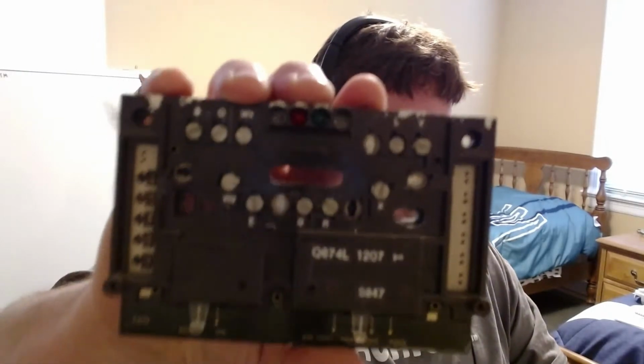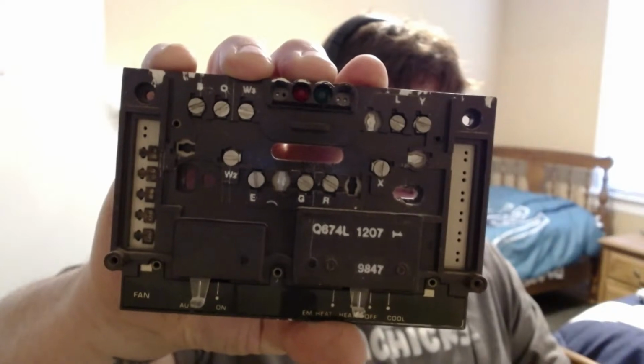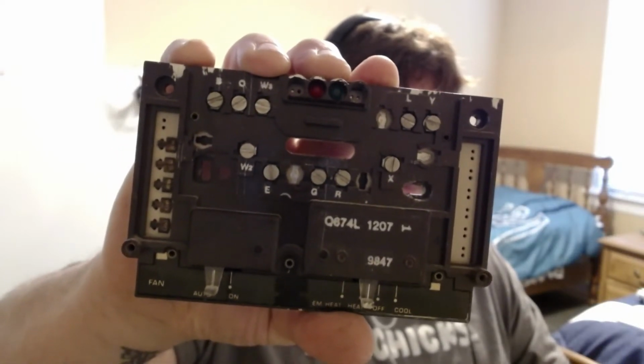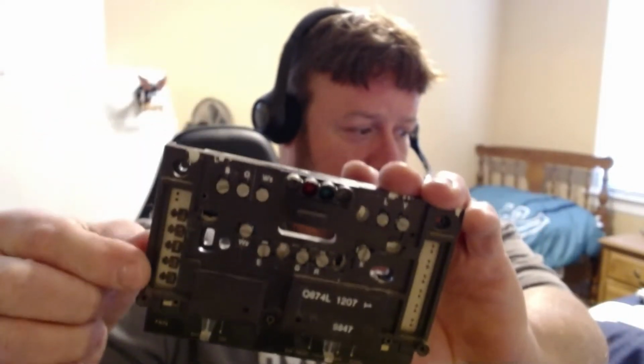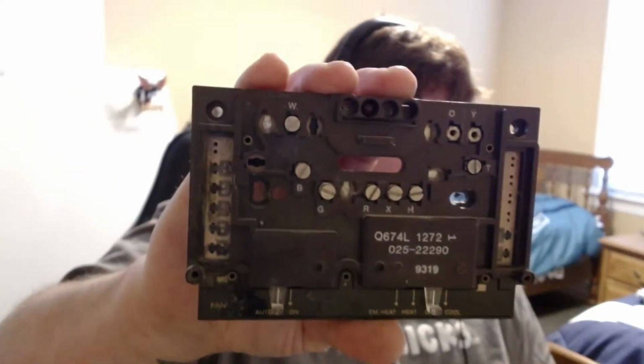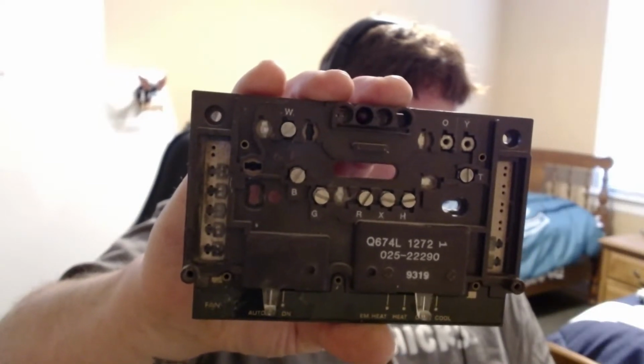It's not going to focus. So it's got Y, L, X, R, G, E, W2, B, O, and W3. And both of these are heat pump thermostat sub bases. So let's try this again. Let's see if it'll. There you go. So again, no common, but X is there for common. And you can see the burn or the heat wear on the tabs here that go on that part there. Same with this one here. X again is common. So these old sub bases, the front cover would sit and that had little metal prongs that attach this, which would communicate back and forth between the two.